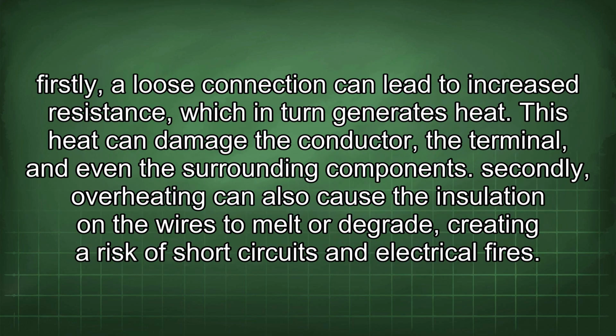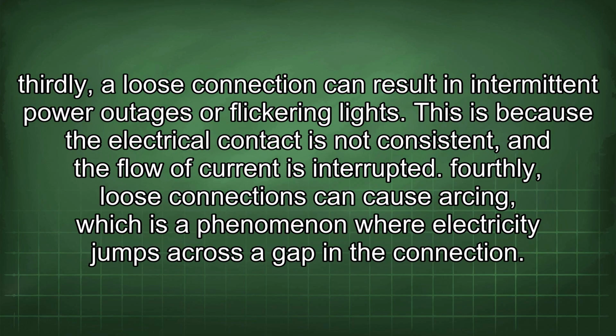Firstly, a loose connection can lead to increased resistance, which in turn generates heat. This heat can damage the conductor, the terminal, and even the surrounding components. Secondly, overheating can also cause the insulation on the wires to melt or degrade, creating a risk of short circuits and electrical fires. Thirdly, a loose connection can result in intermittent power outages or flickering lights. This is because the electrical contact is not consistent and the flow of current is interrupted.